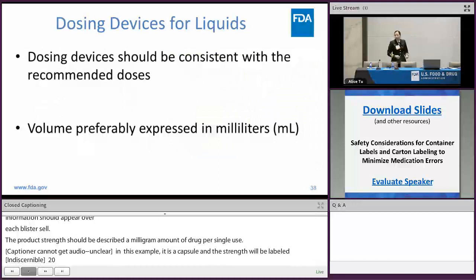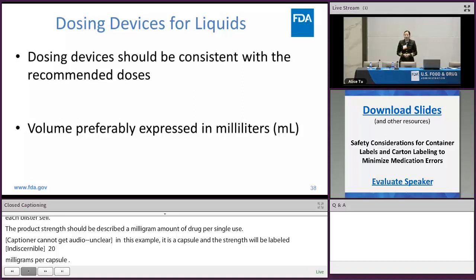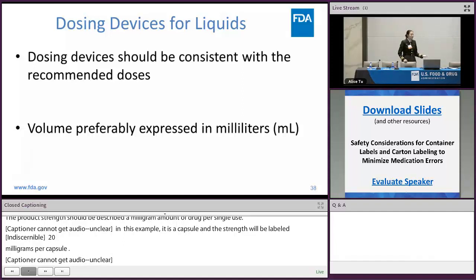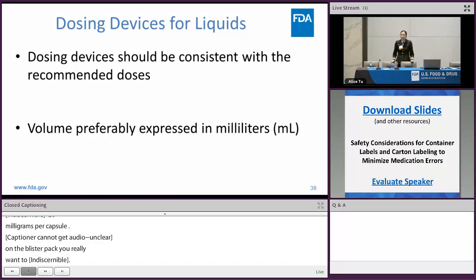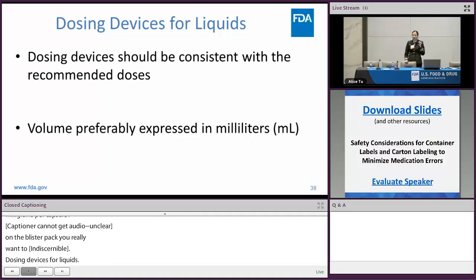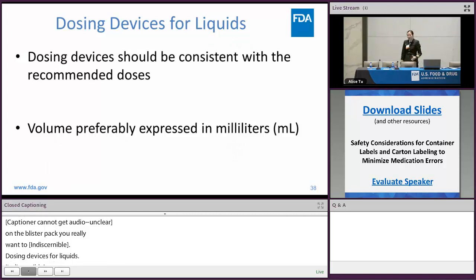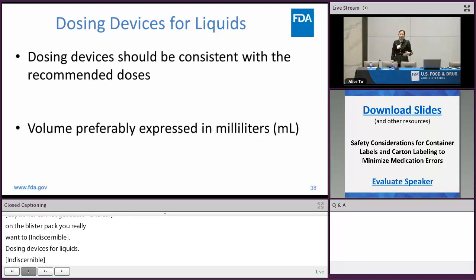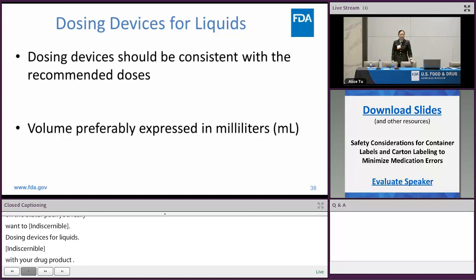Dosage delivery devices for oral liquids: the dosing delivery device, when included or co-packaged with your drug product, should be consistent with the recommended dose. If your dose is 5 mL, the dosing device should have a marking at the 5 mL line. If you have a unique product and the dosing is 17.5 mL, you want a measuring device with a mark at the 17.5 mL mark. Because these are liquids expressed in volume, we preferably ask that you express the markings on the dosing device in milliliters.